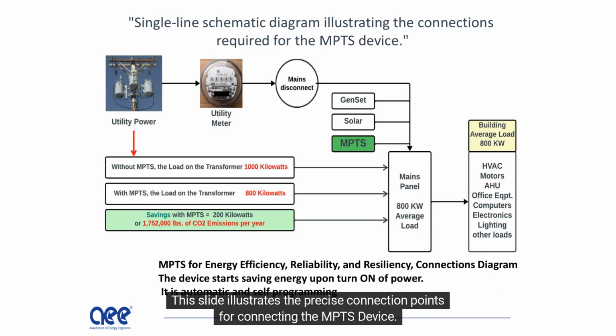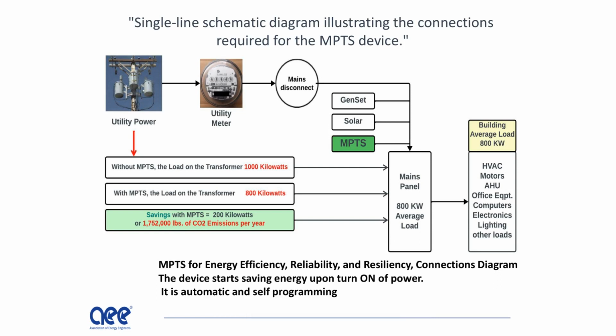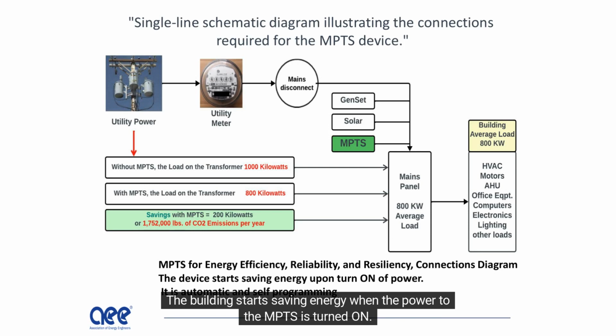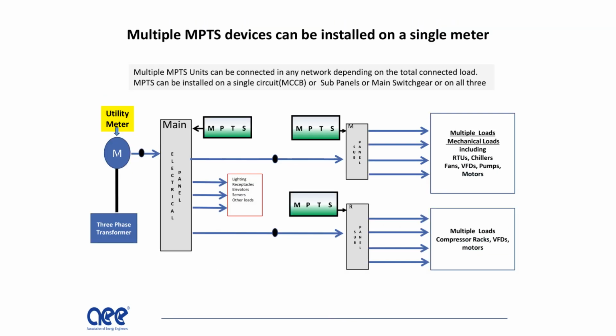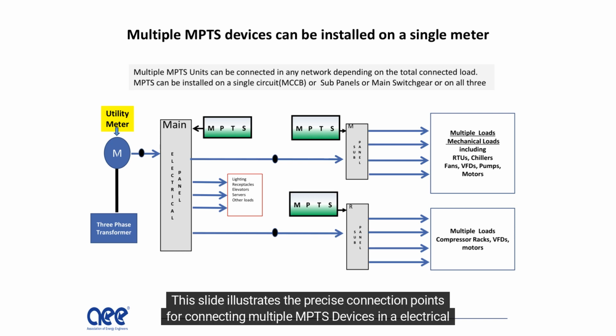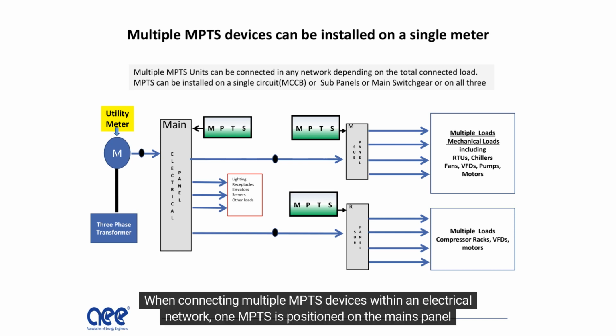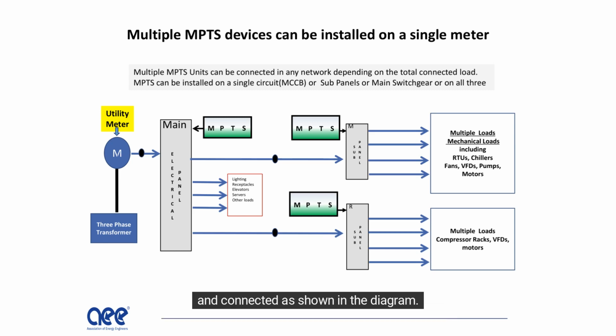This slide illustrates the precise connection points for connecting the MPTS device. The building starts saving energy when the power to the MPTS is turned on. This slide illustrates the precise connection points for connecting multiple MPTS devices in an electrical network. When connecting multiple MPTS devices within an electrical network, one MPTS is positioned on the mains panel and connected, as shown in the diagram.